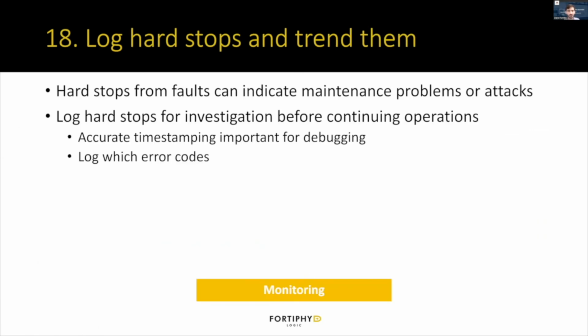Number 18, log hard stops and trend them. Hard stops from faults can indicate maintenance problems or attacks, so it's important to log all that for investigation before continuing operations. And it's really important to have accurate timestamps, so it's easier to understand the sequence of events about what happened when.